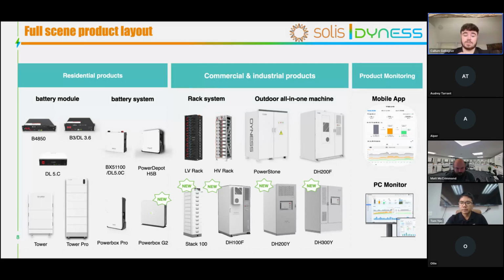We've got the DL5C, a newer product released earlier this year into the UK. It's a 5.1 kilowatt hour module, a newer iteration of the BX51100, which a few of you might be familiar with, with slightly better performance and the 1C rating. Next to the BX51100, you've got the PowerDepot H5B. I will be running through these quite quickly, diving deeper into the ones we want to focus on. That's a 5.1 kilowatt hour module as well, the same as the DL5C, but it is IP65 rated compared to the IP54 of the DL5C.